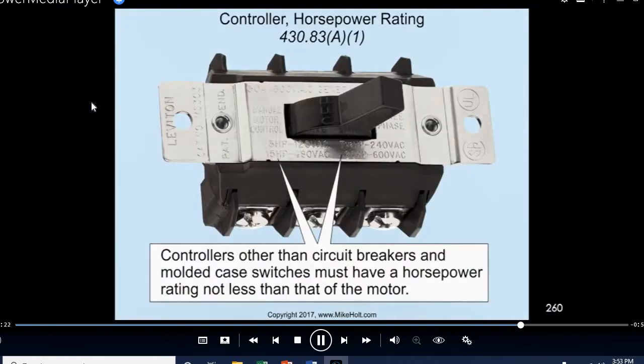Because of that, the UL standard changed so that none of the equipment has to be marked HACR. That doesn't mean you're not going to get something that's marked HACR. The circuit breakers will not necessarily be marked HACR even though they are HACR. You only mark something when maybe something is and something isn't. You got some stuff there that has information about the HACR breakers. Further in there, you see the HACR information. Okay. So controllers have to be horsepower rated unless they're a circuit breaker or a molded case switch.